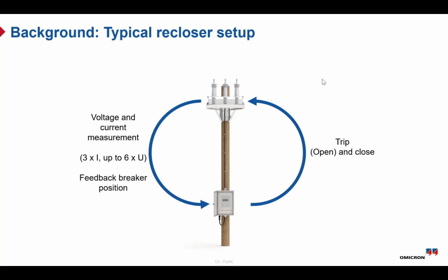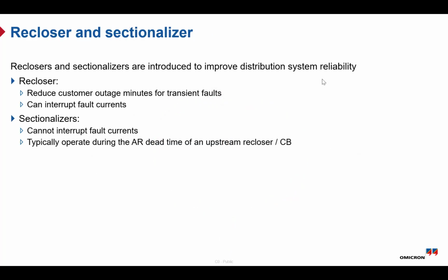There can be additional signals like a manual lockout or a yellow handle status, which tells the controller if the device was manually operated. And finally, we have the control commands. The controller sends trip and close commands to operate the recloser. So in simple terms, we have three main signal groups: measurement, status feedback, and control commands. Understanding these signals is the key for testing because we need to simulate the inputs correctly and verify that the control responds as expected.